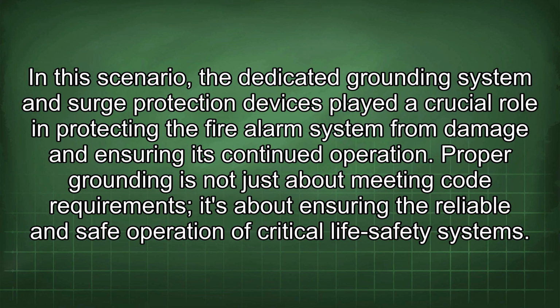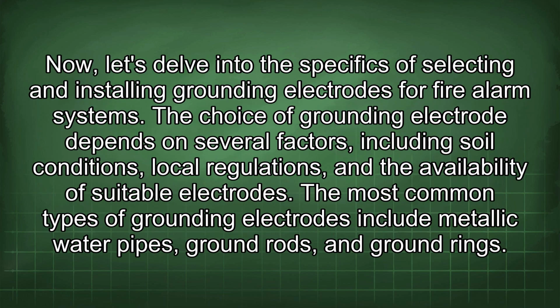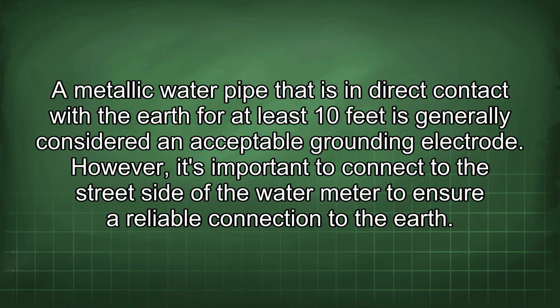Proper grounding is not just about meeting code requirements, it's about ensuring the reliable and safe operation of critical life safety systems. Now, let's delve into the specifics of selecting and installing grounding electrodes for fire alarm systems. The choice of grounding electrode depends on several factors, including soil conditions, local regulations, and the availability of suitable electrodes. The most common types of grounding electrodes include metallic water pipes, ground rods, and ground rings. A metallic water pipe that is in direct contact with the earth for at least 10 feet is generally considered an acceptable grounding electrode. However, it's important to connect to the street side of the water meter to ensure a reliable connection to the earth.